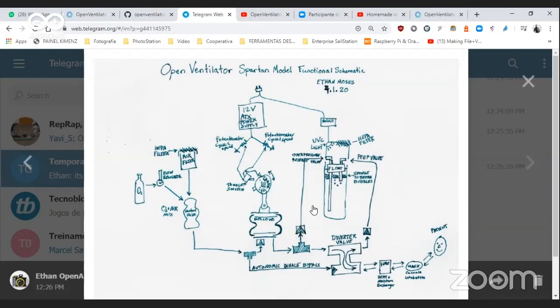So on level 4, we would need very fancy pressure sensors to have a very good precision on the millimeters of water and the curve that this pressure is taking inside the patient's lungs. In my way of seeing, I saw a lot of engineering approaches, but all these engineering approaches have to consider that we have medical concerns that are really, really important. So we have to pump, for example, a lot of air in a short period of time, like 1 second, and the breathe out must be sometimes like in 6 seconds.